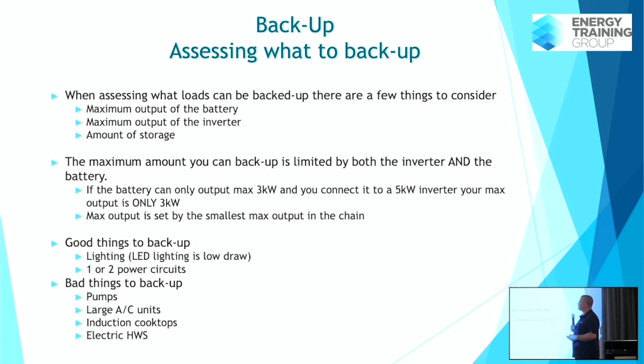Good things to back up when you're installing a standard single phase 5 kilowatt inverter is going to be lighting. Always back up lighting circuits, right? LED lighting, it's a couple of 100 watts. You can always back up the lighting. That's not an issue. And maybe 1 or 2 power circuits, right? But you don't want to be backing up their induction cooktop. You don't want to be backing up their electric hot water service because these things can pull 6, 7, 8 kilowatts just alone. And you might only have a 5 kilowatt inverter on site.